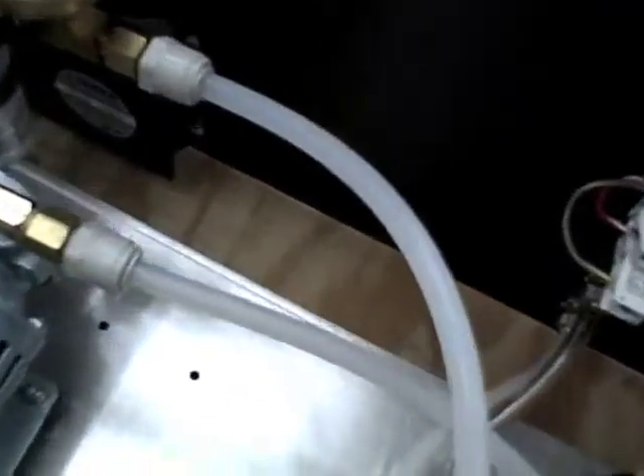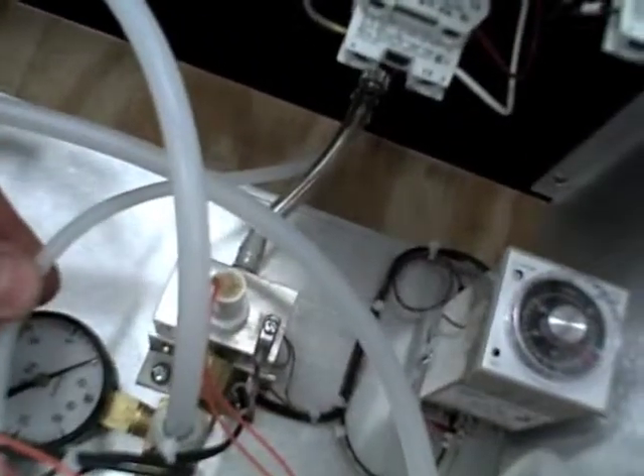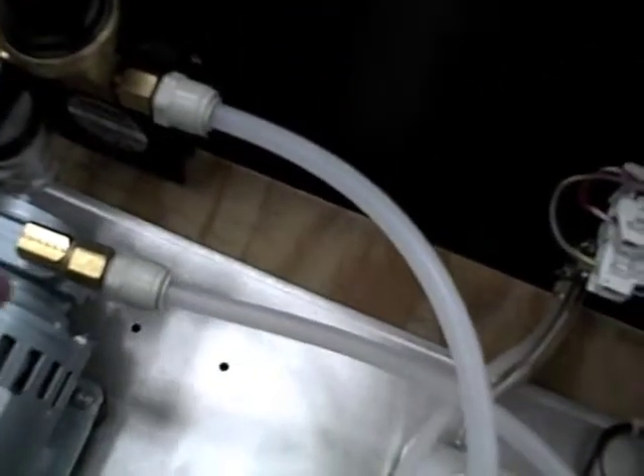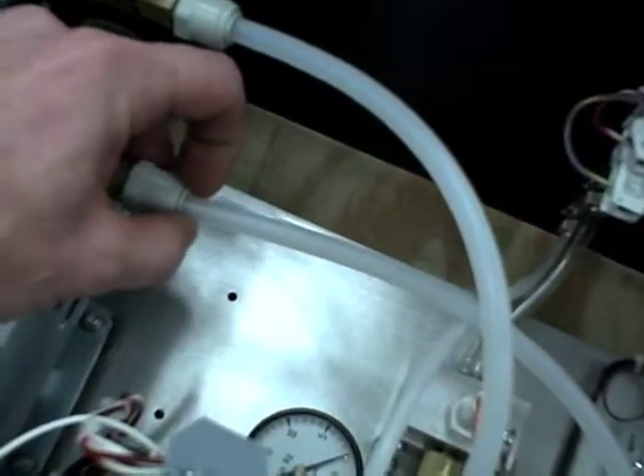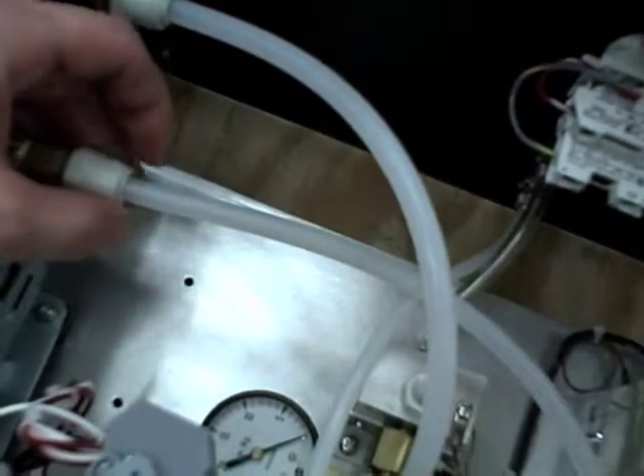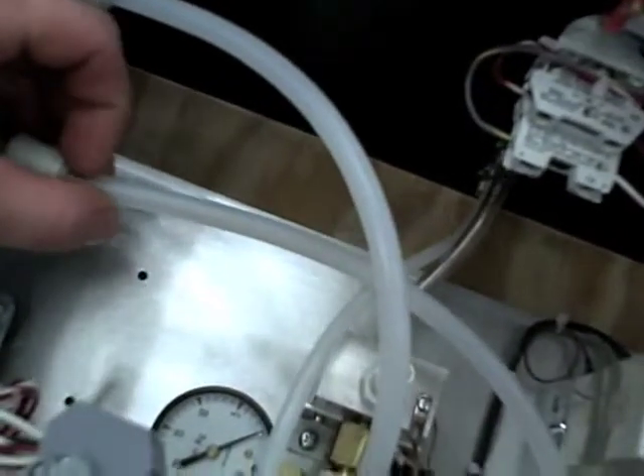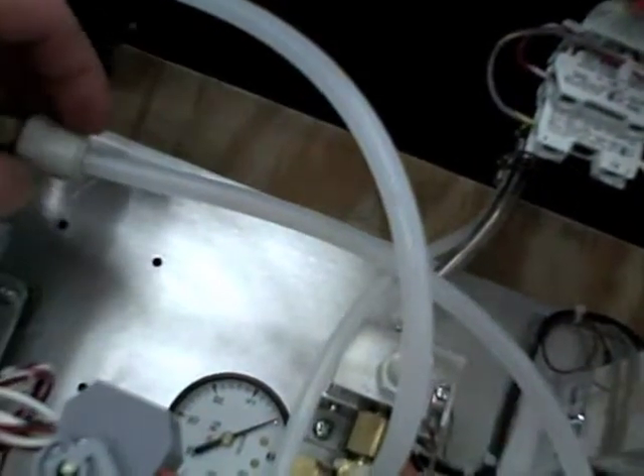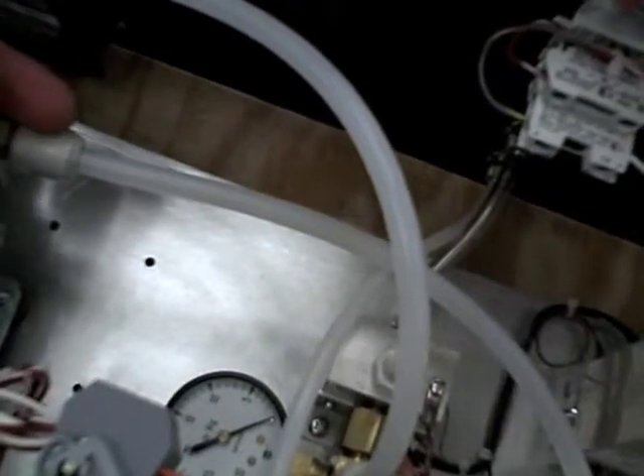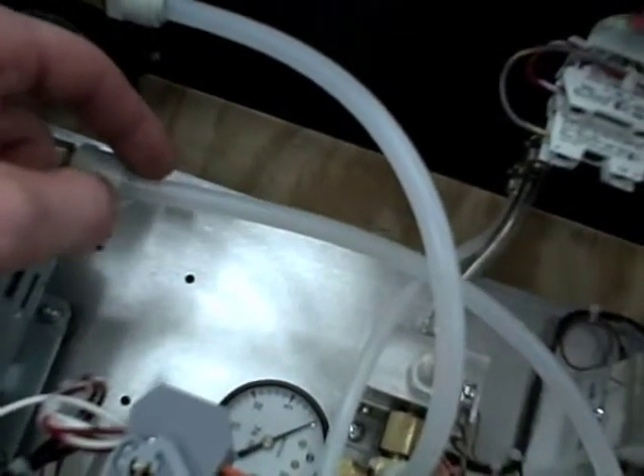You'll see some more vacuum lines and some argon hoses. The main thing to check with the hoses is that they're not burned or kinked, and occasionally you'll want to pull them out of the fittings and just check to make sure that the end of the hose isn't dimpled. Sometimes the O-rings from the fittings will cause a dimple around the hose, and then could cause leaks there. So you want to check those occasionally, but it's not a huge problem.